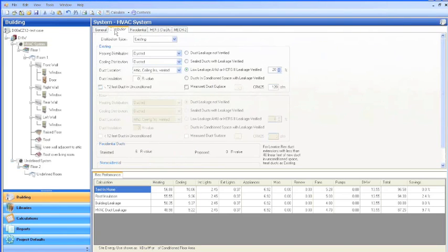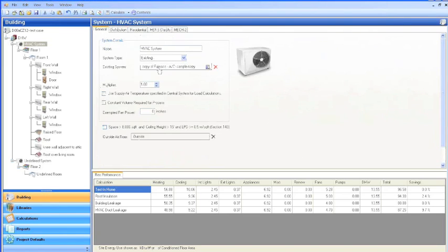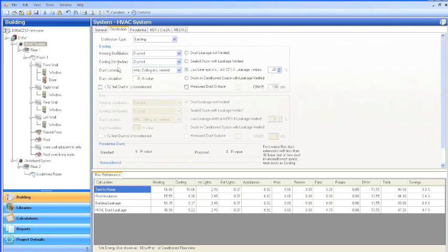Okay, so also I think there was a question about the AHU. This is what you check in order to enter the duct leakage percentage. This is duct leakage to the outside. This is the value that you obtain through a duct blaster test. That's also required of all the advanced projects.